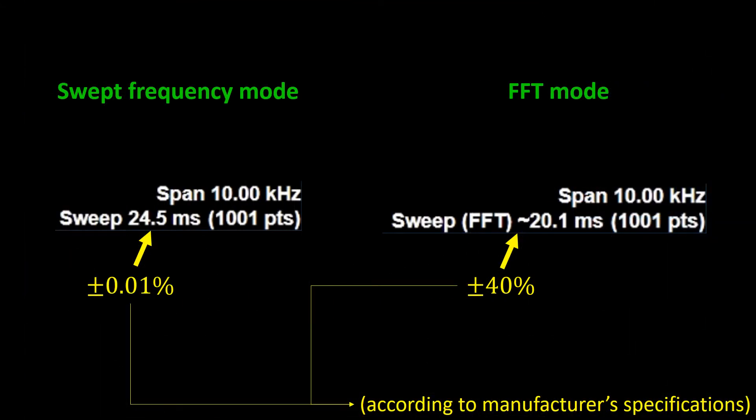The analyzer also displays the sweep time in the FFT mode, but the error in this estimation can be quite large, up to 40% according to the instrument specifications.